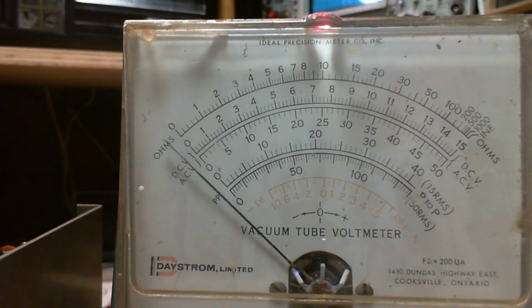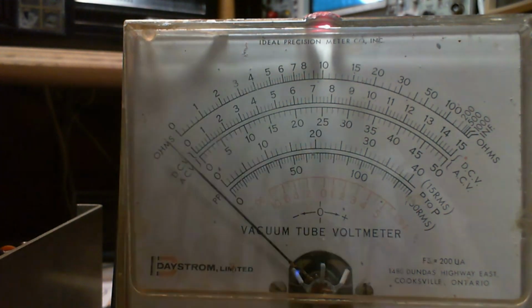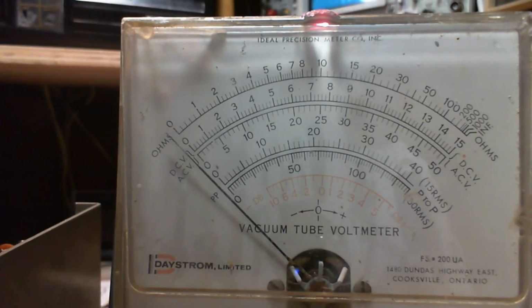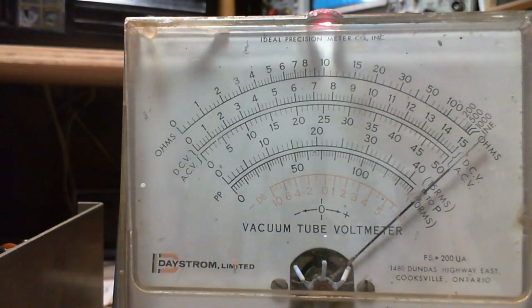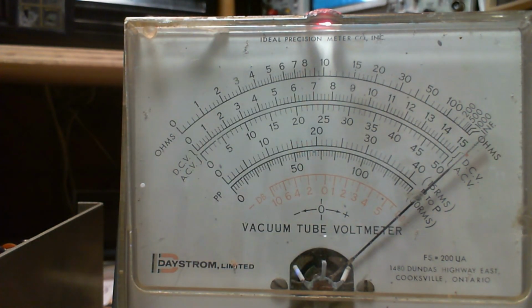Now, what do I have this hooked up to? Nothing. And we'll now connect the meter. Goes right off scale. So we're at 1.52. And on there, I would read that as 1.54 or even 1.55.